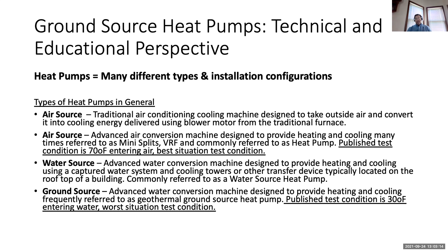It's more like apples to oranges, because 30-degree entering water without freeze protection is fundamentally ice, so your ground source heat pump is heating by using ice. In that worst case scenario, the efficiency of the system goes way up when you improve that incoming water temperature.